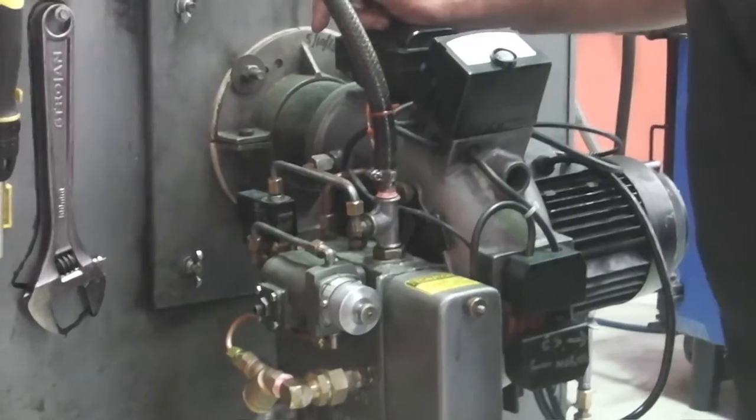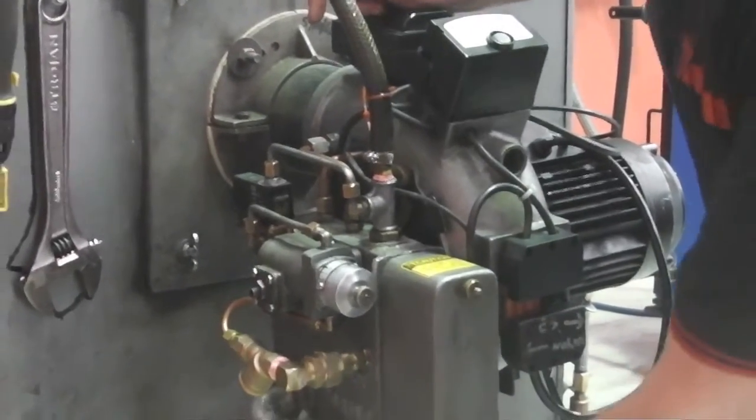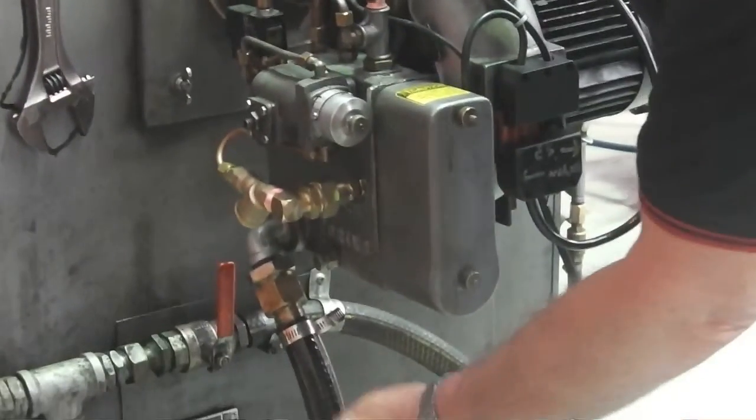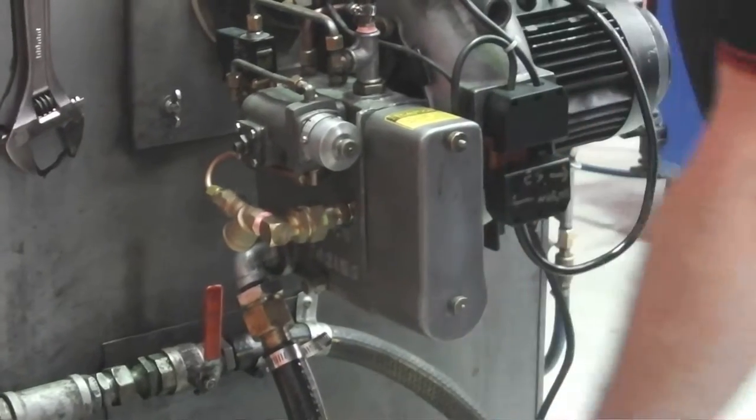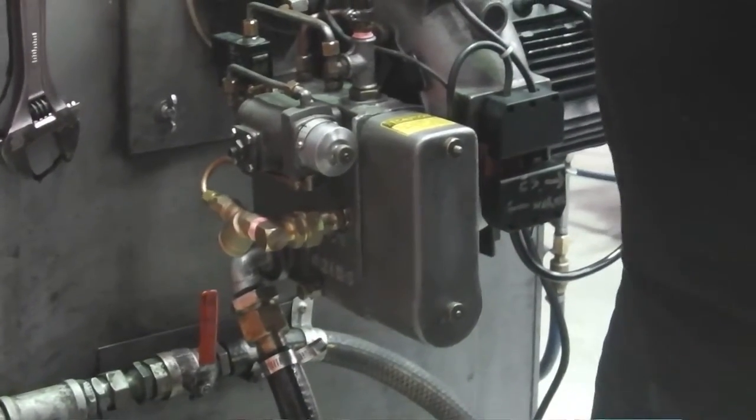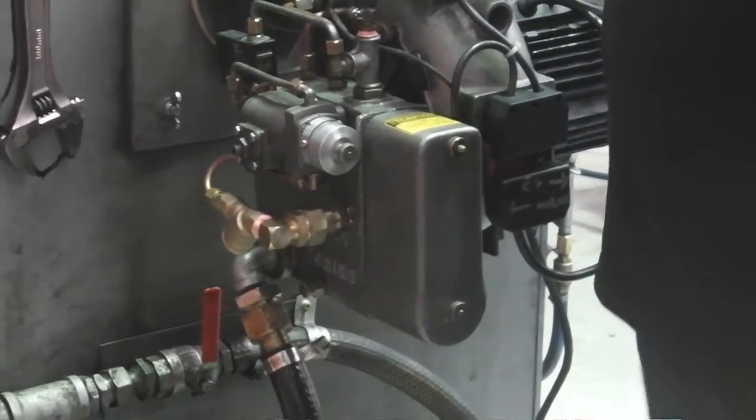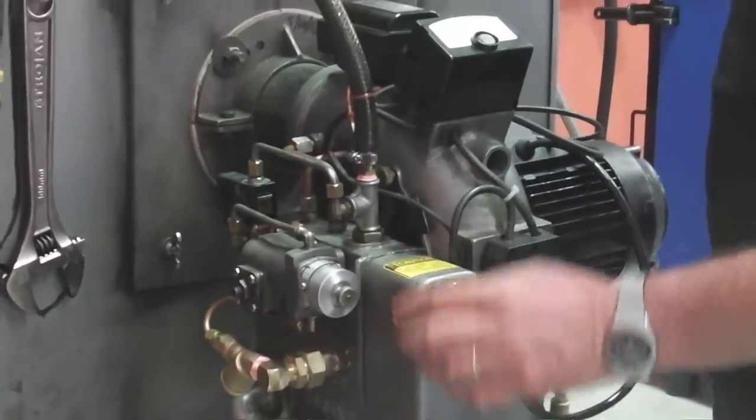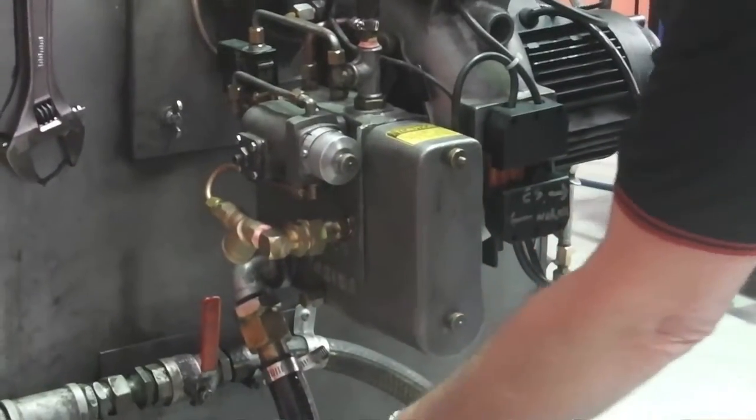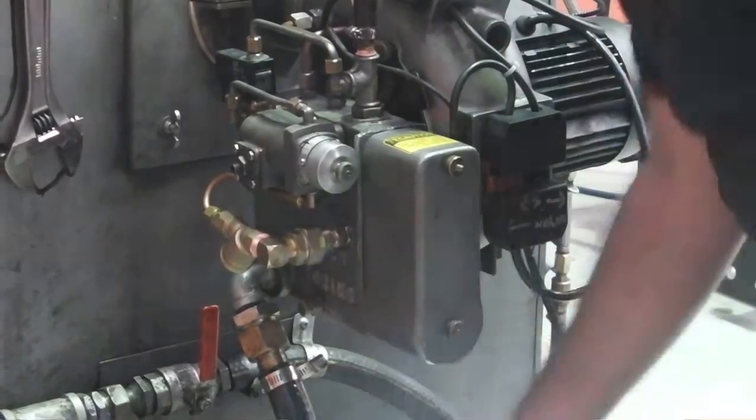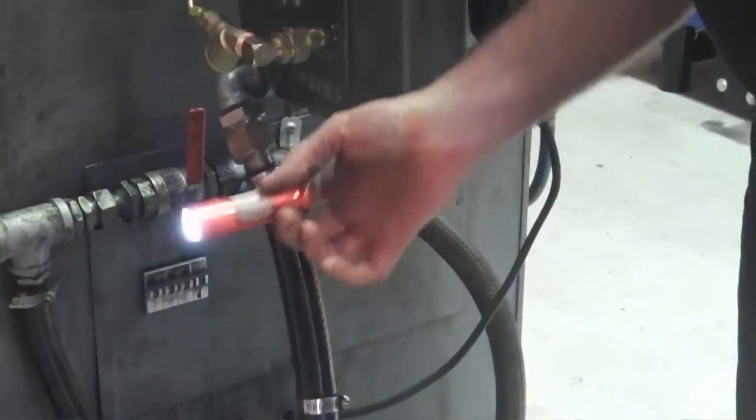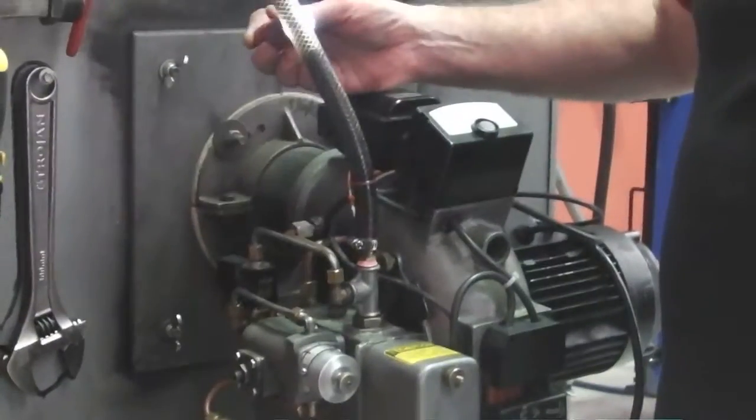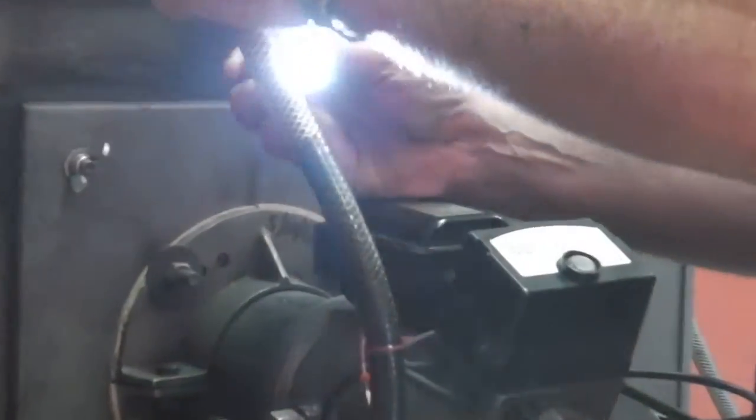Other points of interest is down here we've got the oil supply line. Plumbers and clients, when you're commissioning the burner gun, you obviously have to have oil present in your fuel line here. You can see we've got a torch here. What you have to do is check that the oil comes out of this into this degassing pipe.